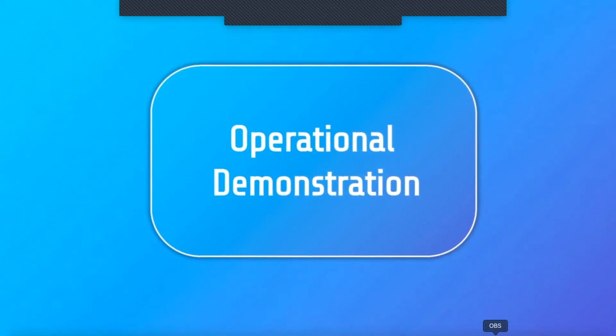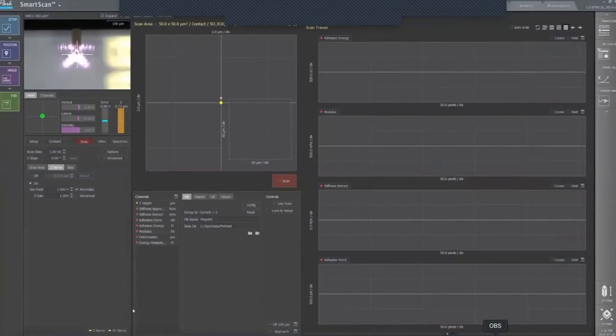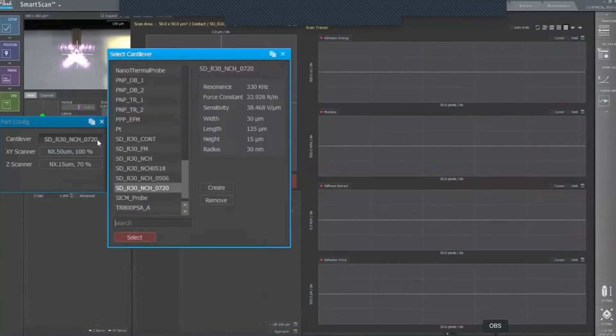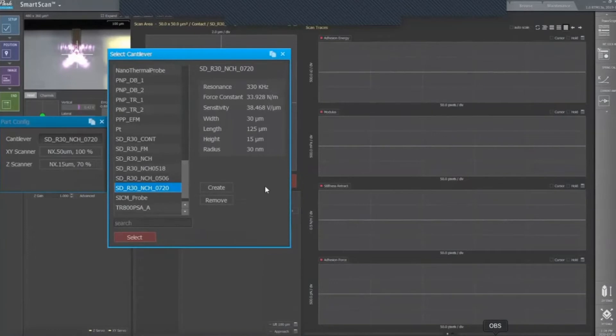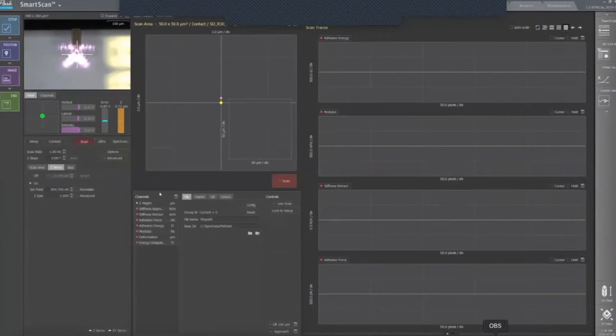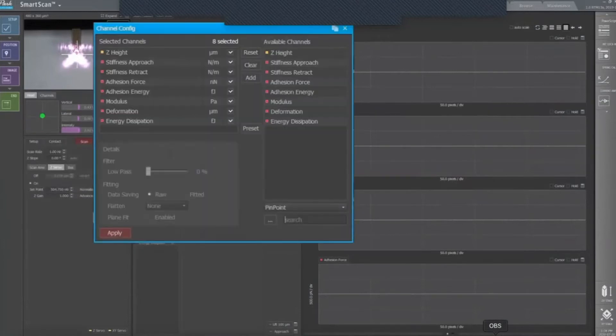For those of you who are not familiar with an AFM operation, here are a few simple steps to follow. First, you will need to select the type of cantilever you want to use. For this application, I will select the cantilever that allows some deformation of the sample and retains high force sensitivity. Carefully choosing the cantilever's spring constant to be compatible with the sample's stiffness is crucial for success with this technique.